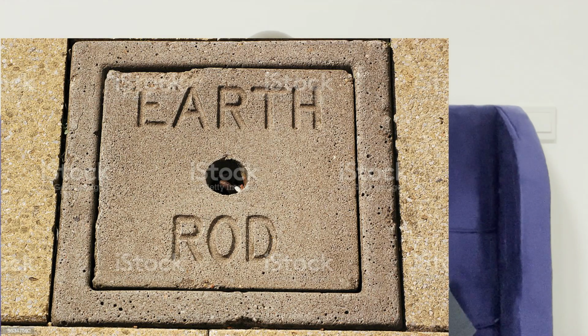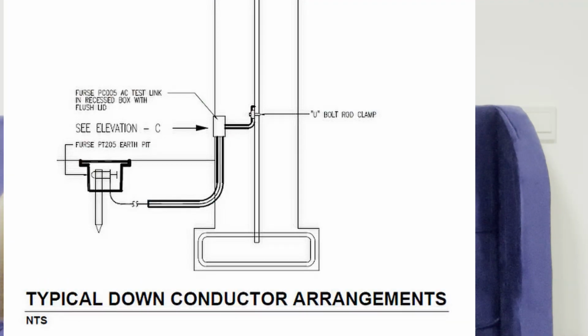If you coordinate things properly when initially building the structure, you can connect to the top of the iron rods or rebars in the columns of your building, since they are vertically continuous all the way down. You connect at the top and then connect at the bottom to the earth rod in the ground, so the rebar in the structure forms your down conductor. That's good planning, and it also makes your building more visually appealing.